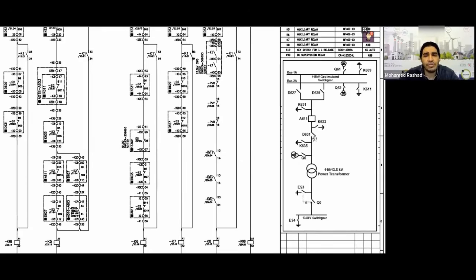You might ask, why not check if the breaker below is open? It's not an issue because even if the breaker below is closed, the breaker here is open, so it's floating anyway. It doesn't matter what's below. And anyway, the interlock we discussed yesterday requires that the breaker below must be open to close this breaker. So it doesn't matter. Okay, so this is easy for you now. All right.